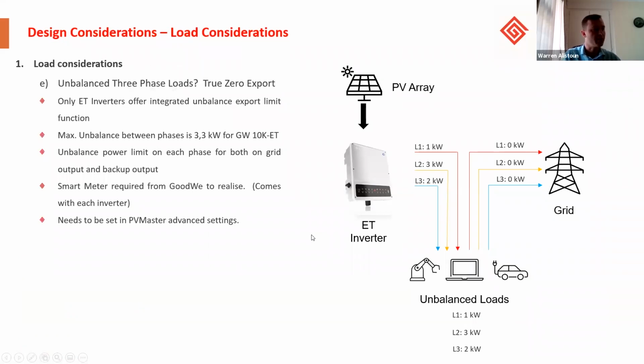Some further load considerations for three-phase applications, specifically in residential homes: the loads are typically always unbalanced. The great aspect about the GoodWe ET inverter is it can support unbalanced loads up to 3.3 kilowatts per phase. That means you can have 0 kilowatts on, say, line 2 and line 3, and still be able to deliver a full 3 kilowatts on line 1. This example here just illustrates the unbalanced load. So you can have 1, 3, and 2 kilowatts over the phases supporting the unbalanced load, and the GoodWe will export 0 kilowatts per phase to the grid.